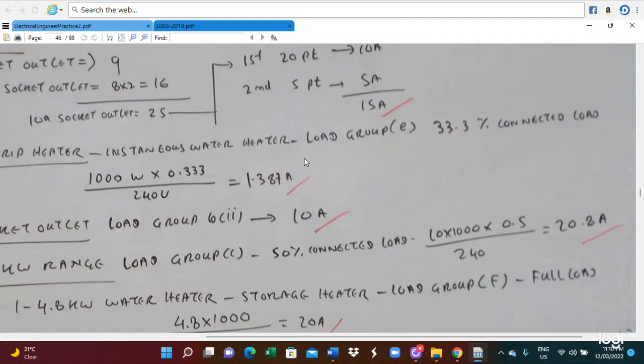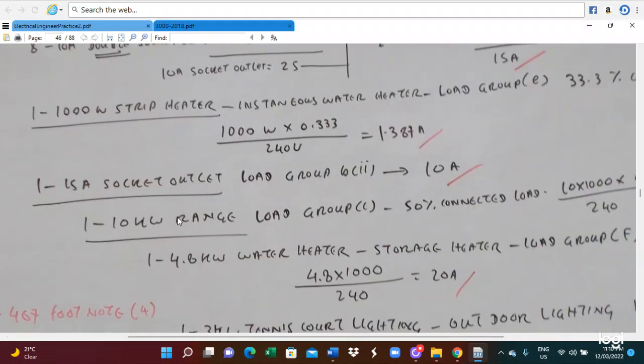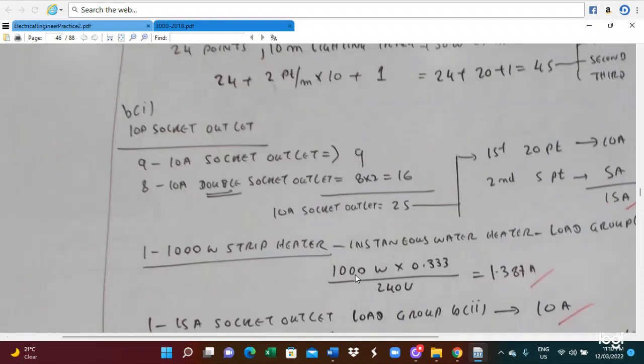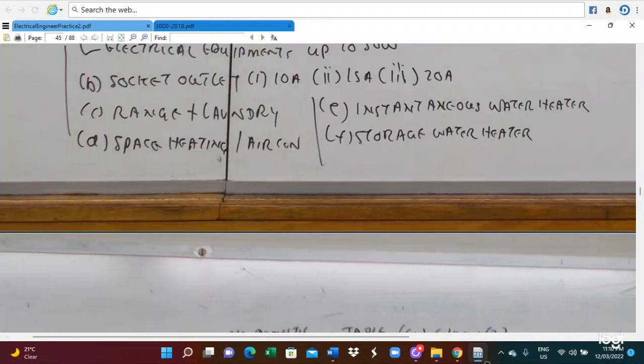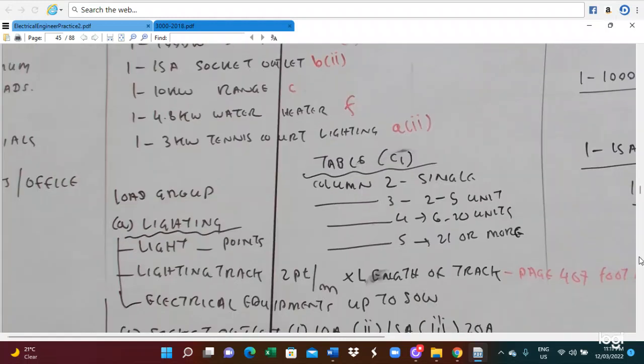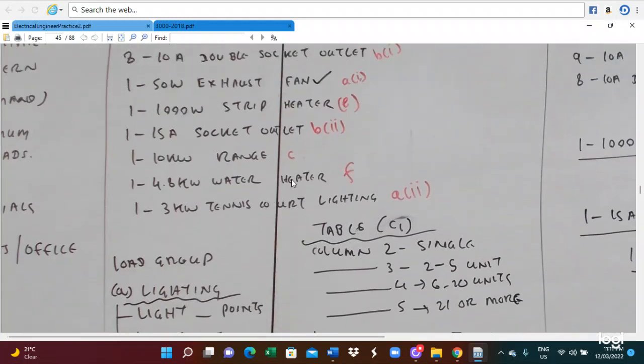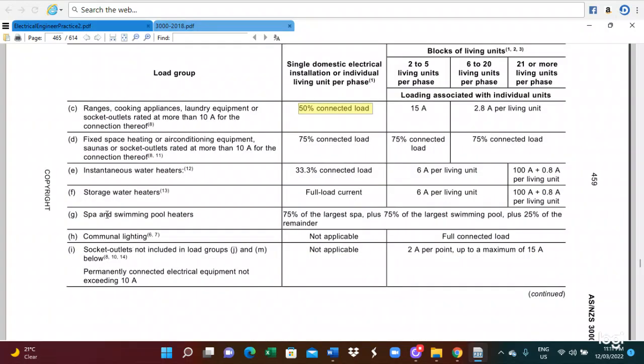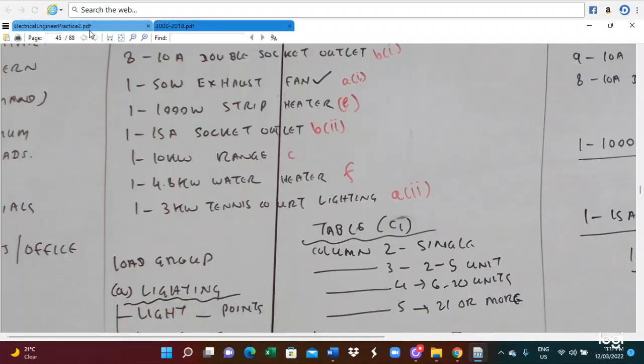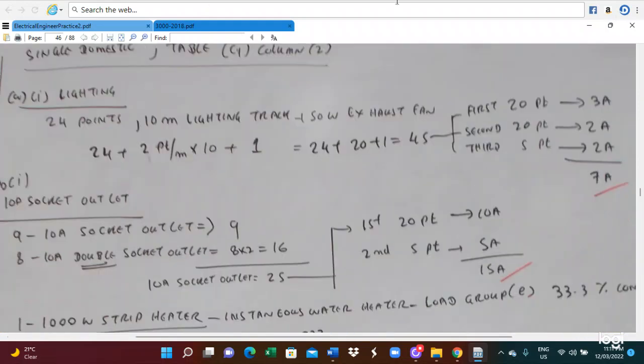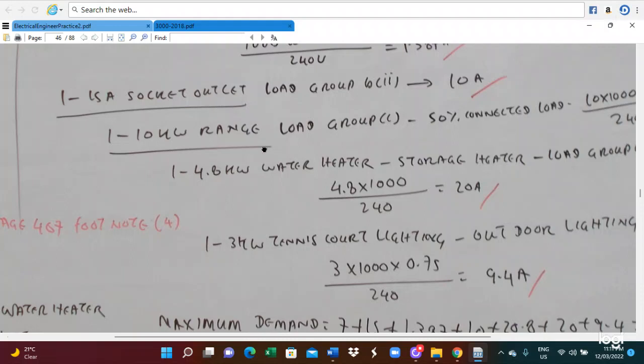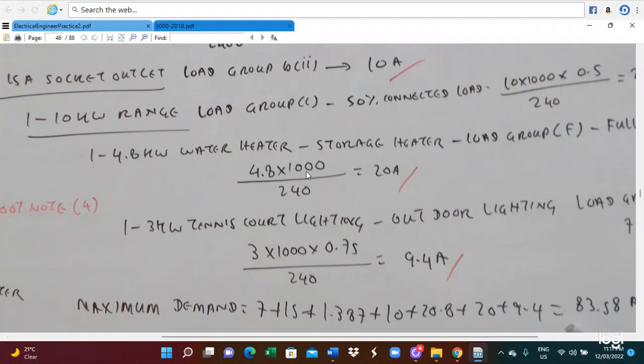Then you also see the 4.8 kilowatt water heater. So here we are also given the 4.8 kilowatt water heater. This is a load group F. So load group F here, water heater. For water heater, you have to take the full current. So for the 4.8 kilowatt, we take the full current. 4.8 multiplied by 10 power 3 and divided by 240, you get the current of 20 ampere. So this load draws 20 ampere.